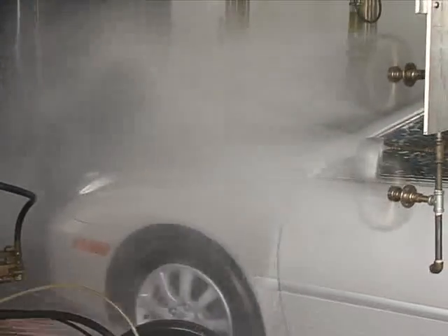...a lot of times I've seen that we get that 60 PSI with one valve open, but when we open all those valves, we drop sometimes below 20-25 PSI. So we're not asking for more water — we're just asking for what they tell us they'll give us, and we're going to manage that within our own facility.